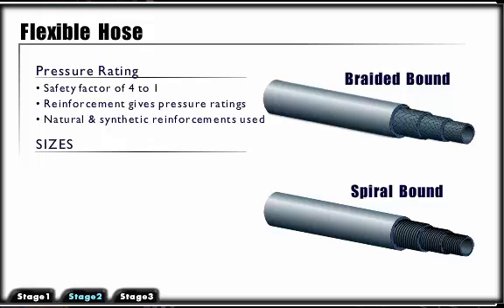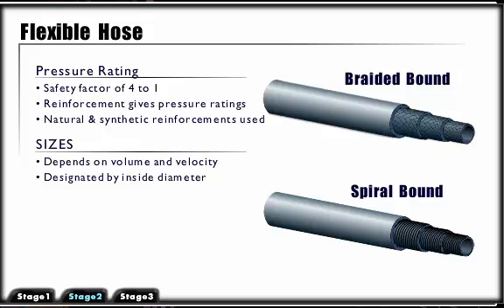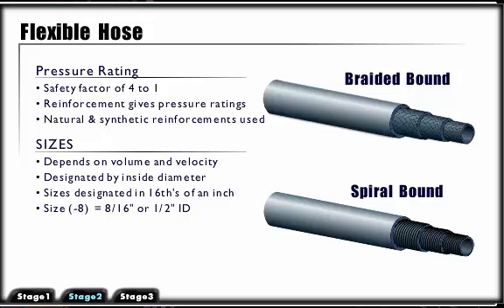Required hose size depends on the volume and velocity of the fluid flow. Unlike pipe and tubing, hose sizes are designated by ID or inside diameter. Sizes are designated in sixteenths of an inch using a dash and a number equivalent to the numerator of the fraction — for example, dash 8, or 8 sixteenths, or half-inch ID.